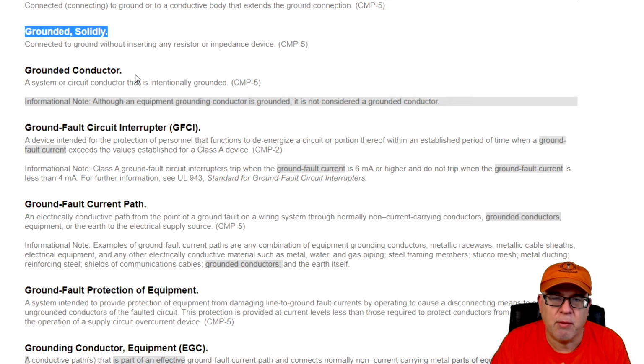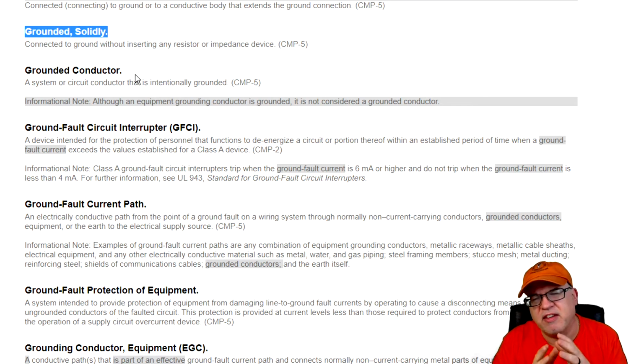All right, next one is the term solidly grounded. That's a connection to ground without inserting any resistor or impedance. We have some applications where we have a high resistance ground system, and then we have what's called a solidly grounded system. So from a transformer XO to the ground, or from the XO over to the case, and everything connects to earth through your electrode system, there's nothing in that path on the supply side bonding jumper. Excuse me, system bonding jumper. Too many terms. The connection from the XO to case, there's no resistance in there, no resistor or impedance device. So we would consider that solidly grounded.